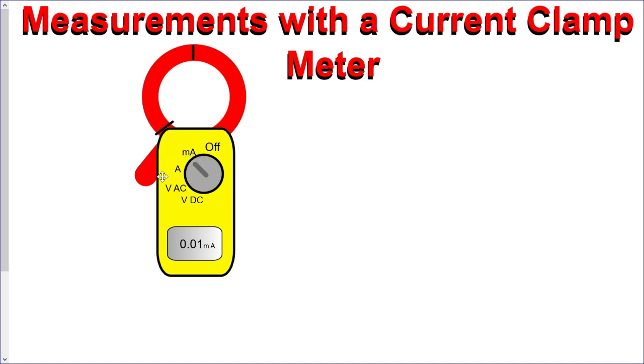Obviously, with the changes that have happened in relation to selection of RCDs, it's vitally important that when we are having a look at measuring installations, particularly for periodic inspections, it's vital that we measure these DC components that might be getting inserted back into our RCD's toroidal core.